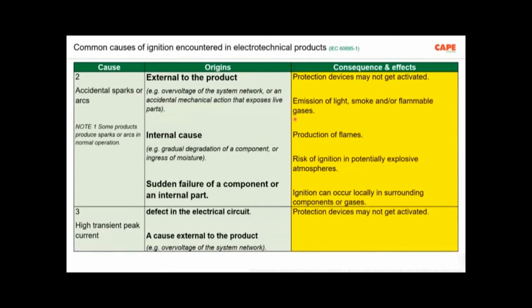Number two, accidental sparks or arcs. Here, we must understand that there are some electrical apparatus which inherently create arcing while operating. But that arcing is not supposed to ignite a fire. That is much more important. Then accidental sparks or arcs. How does it happen? It can be external to the product. For example, overvoltage of the system network. What does it mean? System network means the electricity supply.